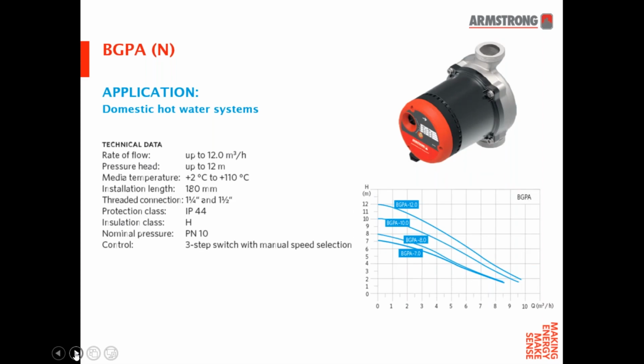BGPA-N, again, the application is domestic hot water systems, but here a bit of a higher capacity. So the rate of flow increases to 12 cubic meters an hour. The pressure head is up to 12 meters. Media temperature exactly the same, 2 to 110 degrees centigrade. And the installation length in this model is purely just 180 millimeters face to face. Threaded connections can either be an inch and a quarter or an inch and a half. And the IP rating is IP44.